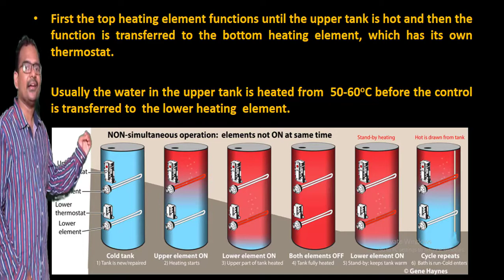Now let's see the operation. Initially, the top heating element functions until the upper tank is hot, and then the function is transferred to the bottom heating element, which has its own thermostat. Usually, water in the upper tank is heated from 50 to 60 degrees centigrade before control is transferred to the lower heating element when hot water is consumed. Once again, cold water enters through the dip tube and the process repeats.